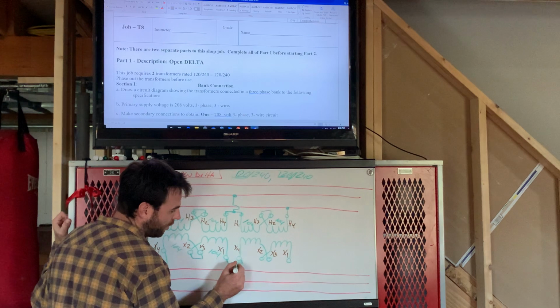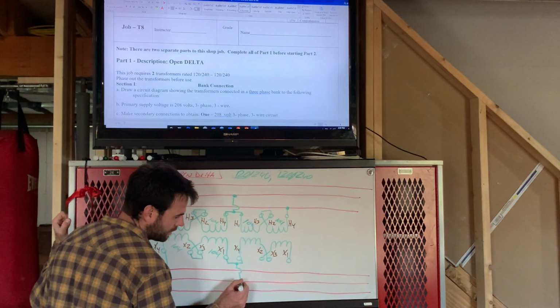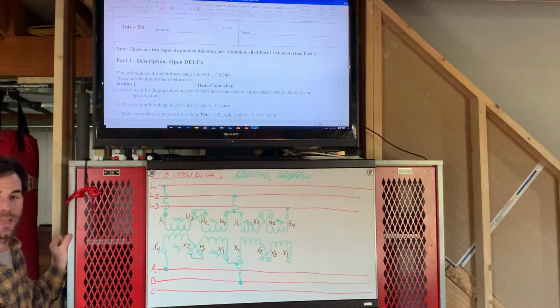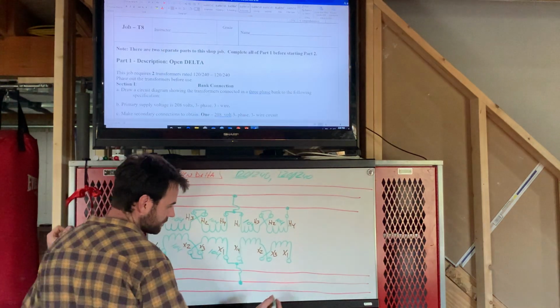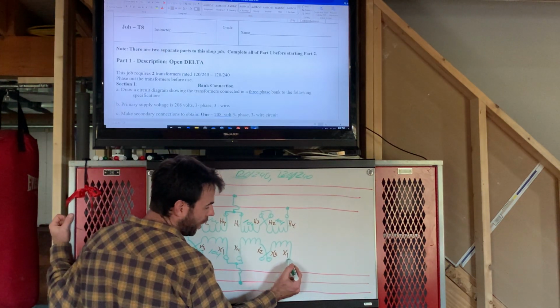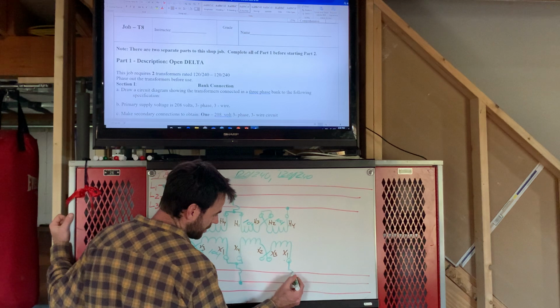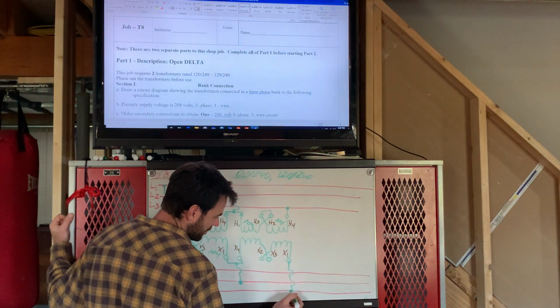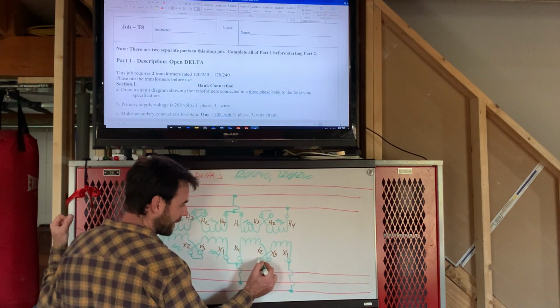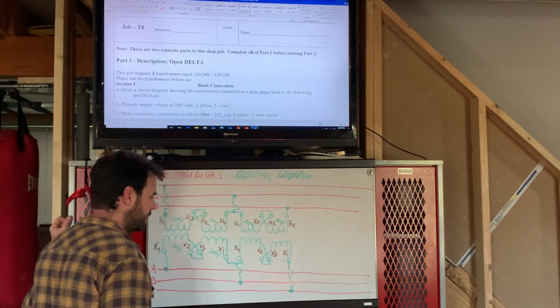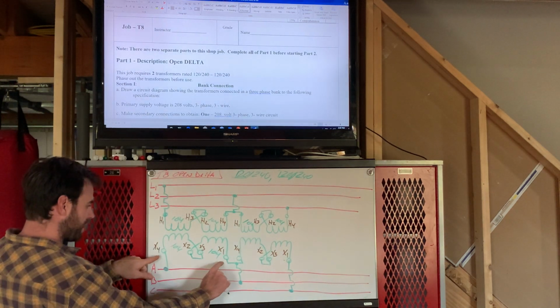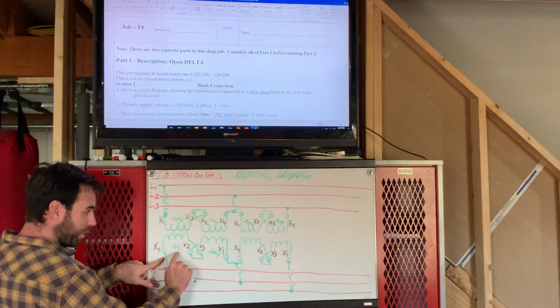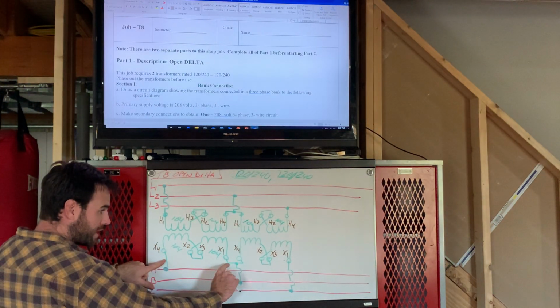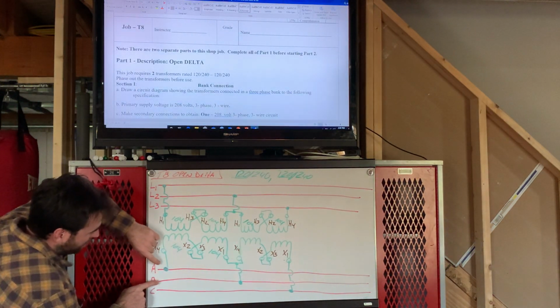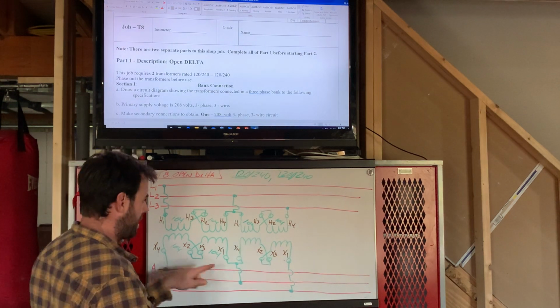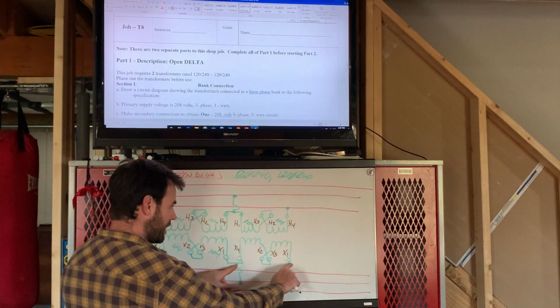Off of that common point, come down. That's going to make up my B phase. Now I'm going to come off of X1 of my second transformer. Jump X2 to X3. So now between this point and this point, I have 208 from the 104 to the 104 in these coils. Here's 208. So essentially it's 208 volts between A and B. I measure between here and here.